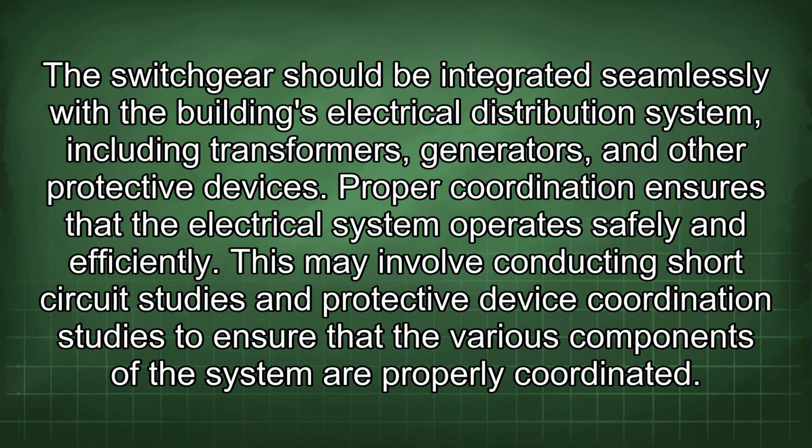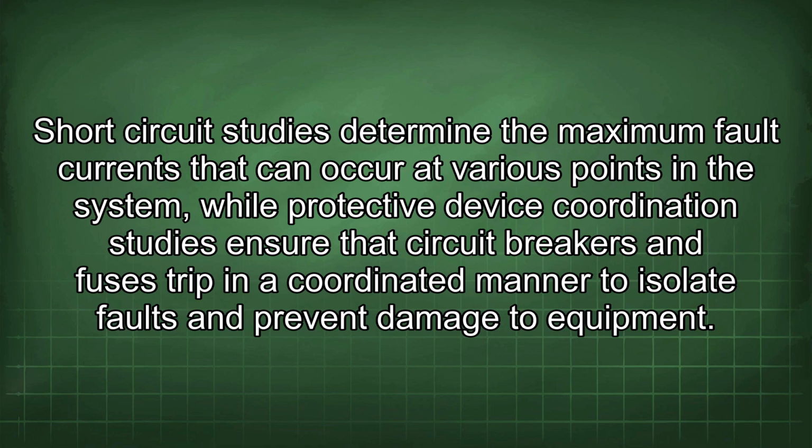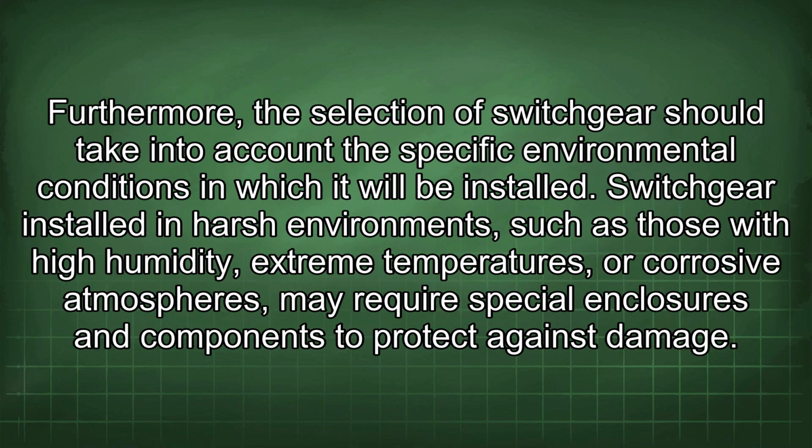This may involve conducting short-circuit studies and protective device coordination studies to ensure that the various components of the system are properly coordinated. Short-circuit studies determine the maximum fault currents that can occur at various points in the system, while protective device coordination studies ensure that circuit breakers and fuses trip in a coordinated manner to isolate faults and prevent damage to equipment.